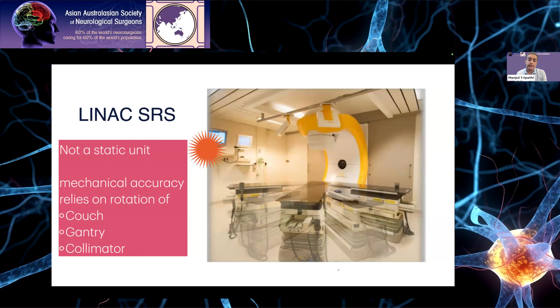This is a new LINAC-based machine, the gyroscopic radiosurgery system called the ZAP-X, and it has significantly improved in comparison to its earlier LINAC-based counterparts, especially the CyberKnife. The mechanical accuracy is now submillimetric, but the sharp dose fall-off and the mechanical accuracy of gamma knife are still slightly better. Because the source to target distance is least with the gamma knife, the penumbra and its particular 50% isodose fall-off, the dose gradient, are extremely steep in gamma knife, providing accuracy of treatment delivery while sparing your neighborhood.